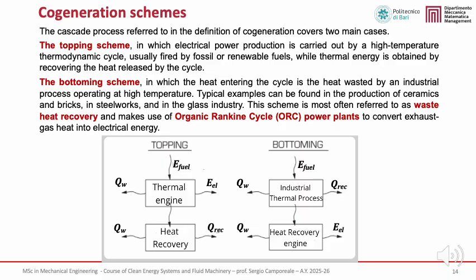This is the most common cogeneration configuration, and it includes technologies such as gas turbines and internal combustion engines with heat recovery. In contrast, the bottoming scheme starts from an industrial process that already operates at high temperature. In this case, the waste heat produced by the process is recovered and supplied to a power cycle, which converts part of this thermal energy into electricity.